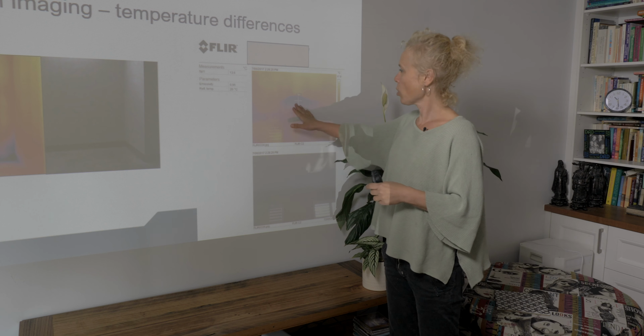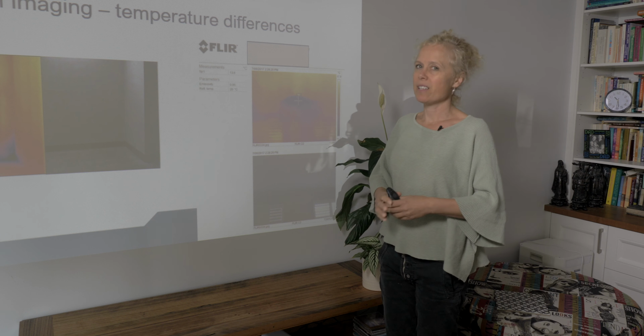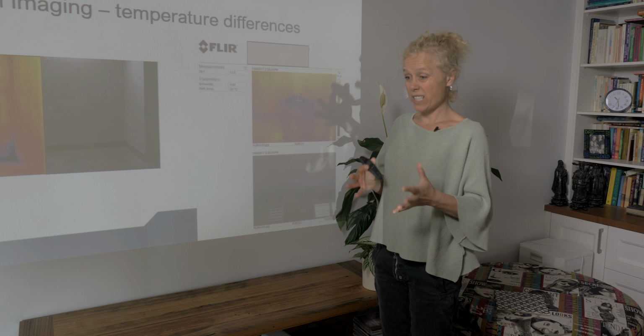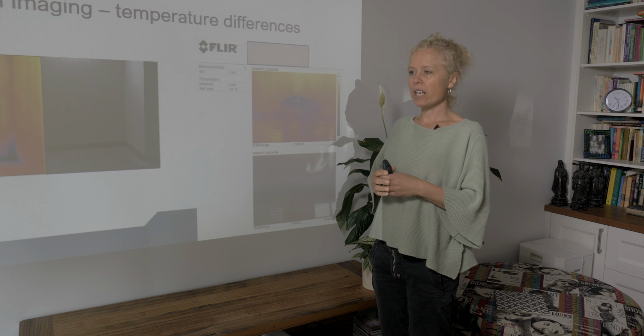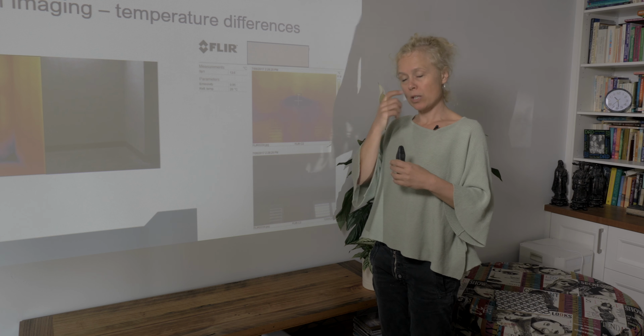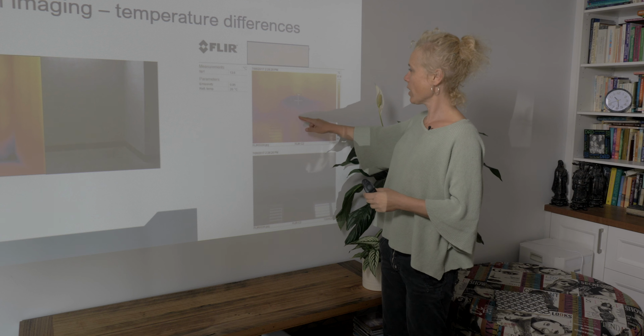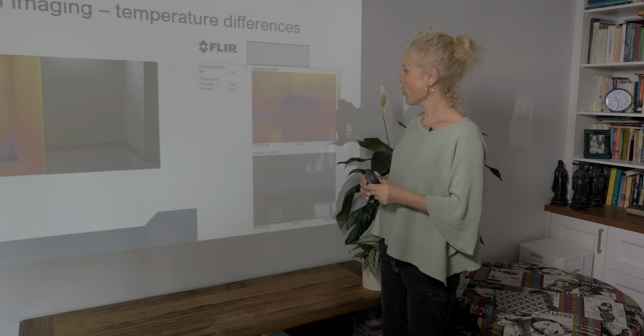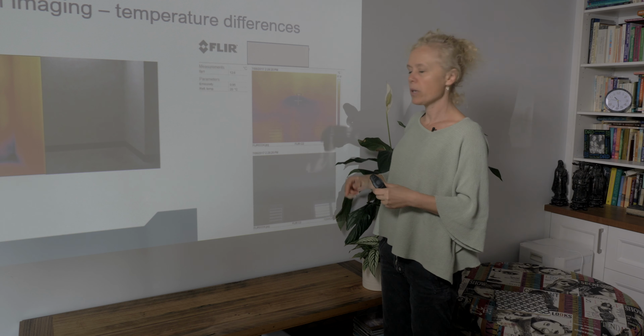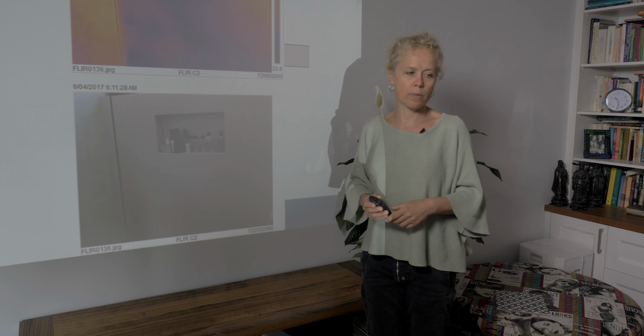If you see these blobs and they're regular shape, then that's not generally water, because water isn't regular. They'll often be like with ghosting, which we'll talk about later in the course, where the noggings are, for example. So you're looking for irregular shapes like how water would flow and these darker colours, but you have to verify it with your moisture meter.